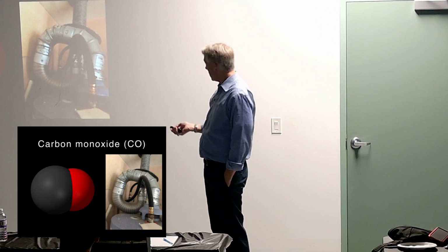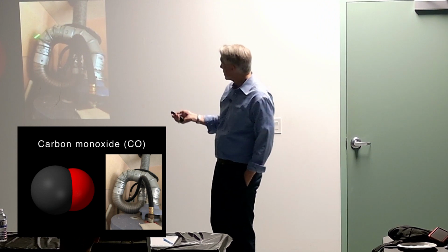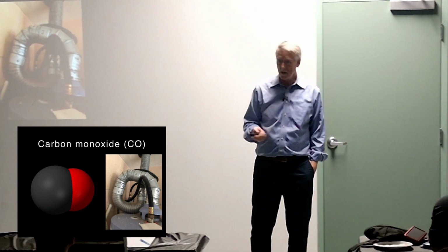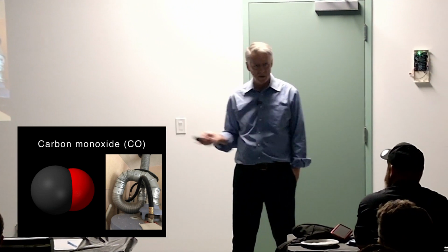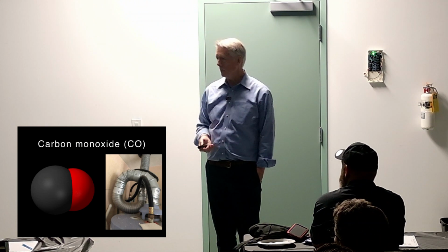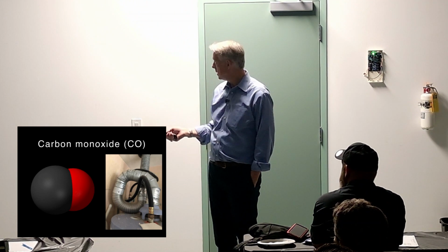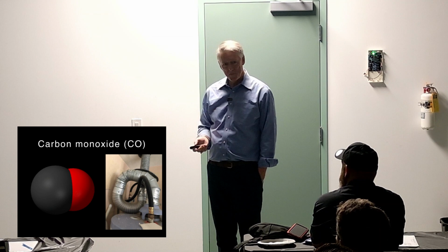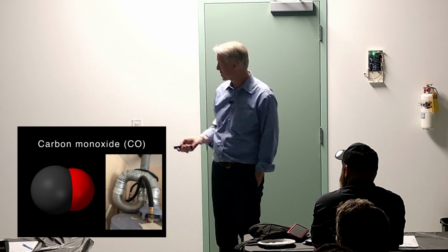and that can cause severe problems, depending on how high the level is. One way to guarantee that you get carbon monoxide is to do something like this. Anybody seen a heat pump? Sorry, not a heat pump. A water heater trap in the flue? I've never seen them like that. Good. This is very dangerous.